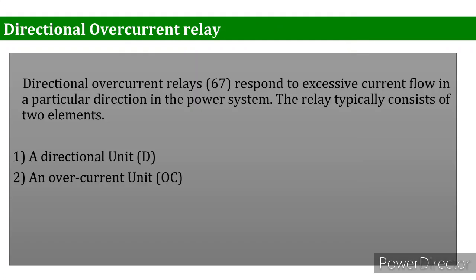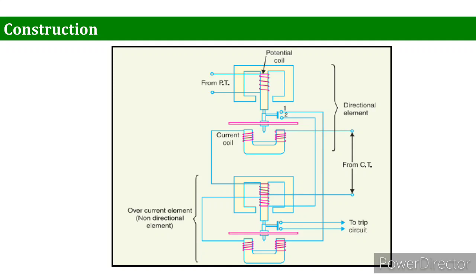The directional overcurrent relay, with ANSI number 67, responds to excessive current flow in a particular direction in the power system. The relay typically consists of two elements: a directional unit and an overcurrent unit. In a previous lecture on overcurrent relay, we did not take the direction of current into account — this relay addresses that, dealing specifically with the direction of overcurrent.